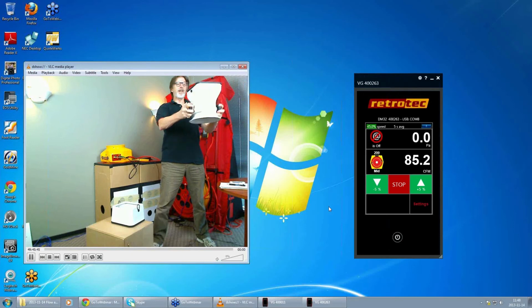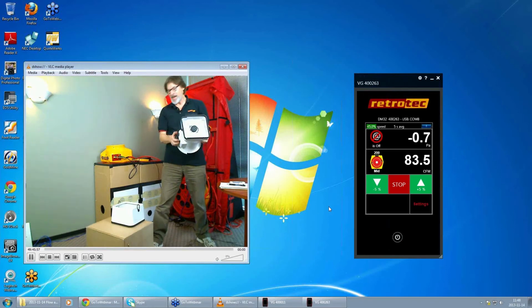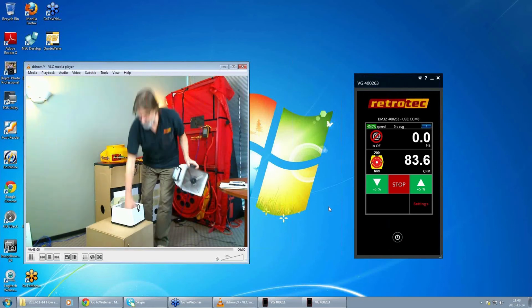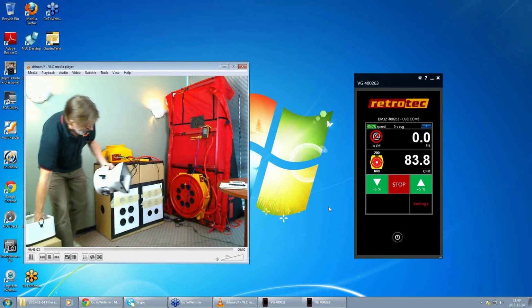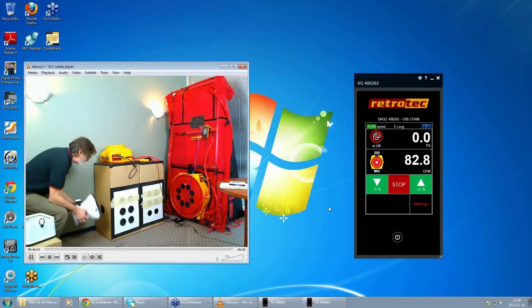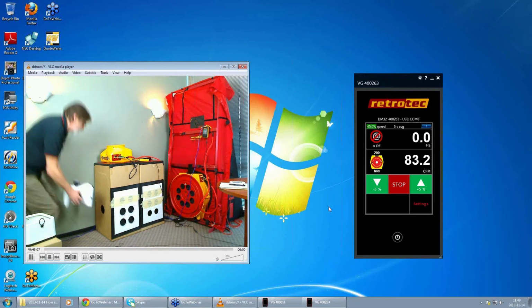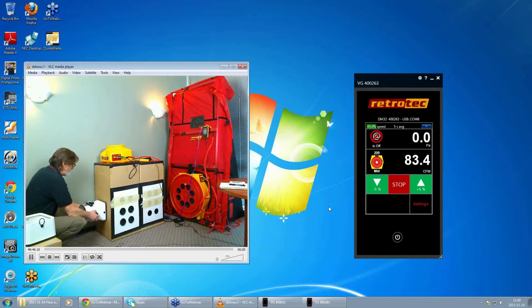And because it's powered, if you have a little bit of leakage around here, it doesn't matter, because it will neutralize the pressure on this plane to 0. And even if you make measurements where there's a pretty big gap, it'll still give you a pretty accurate result. So I'm going to do a little demonstration here. We're on exhaust mode, so let's say this is an exhaust fan. I just pressed the little button, and I don't know if you can see the fan spinning there. I don't think you can. Maybe just in the corner there.